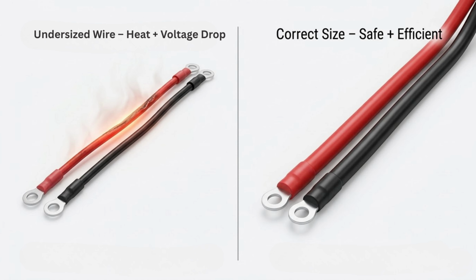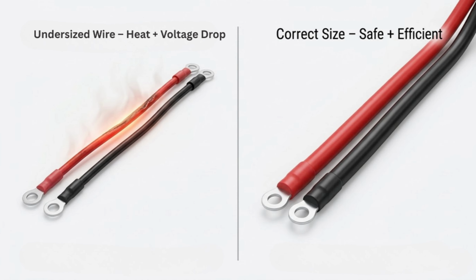When wiring is poorly planned, 2 big problems usually show up first. The first is heat buildup. Resistance in wires or connections turns electrical energy into heat. In a battery compartment or enclosed cabinet, that heat can damage insulation, degrade components, and trigger shutdowns. The second is voltage drop. When the wrong wire size is used or cable runs are too long, appliances may not get the voltage they need. Your inverter may complain, performance drops, and the whole system becomes less dependable.